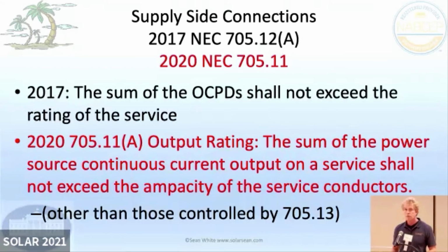And so these things will just control the currents. And it kind of makes sense. If you think about it, if you have a PV inverter and a battery inverter, you're not going to blast both of those full speed at the same time feeding the grid, because when the PV is going at full speed, you're charging the battery, you're not discharging the battery. So as long as we control those things together and make sure that we're not blasting them both out to the grid at the same time, then things are going to be safer. And that would have to do with power control systems. And then also throw in a bidirectional EV, which is kind of just an energy storage system, really.